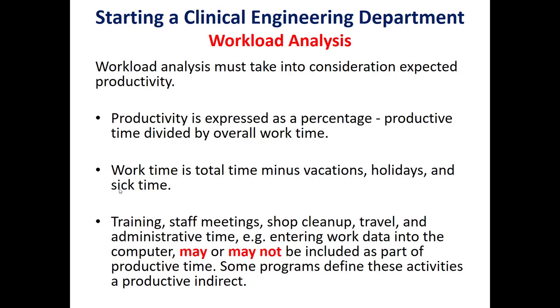Now we will move to the second point, which is the workload analysis for a clinical engineering department. Workload analysis must take into consideration the expected productivity. Productivity is expressed as a percentage: productive time divided by overall work time, multiplied by 100. Work time is the total time after subtracting vacations, holidays, and sick time. Depending on the hospital, it may also exclude training, staff meetings, shop clean-up, travel, and administrative time.